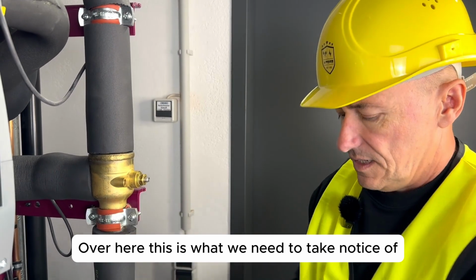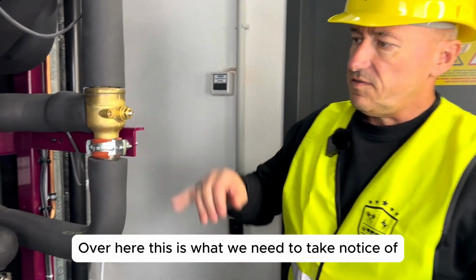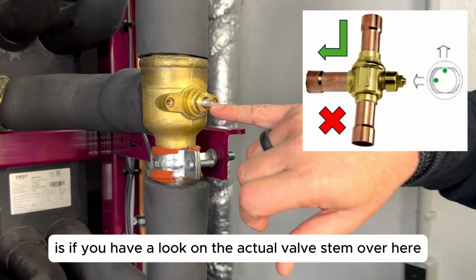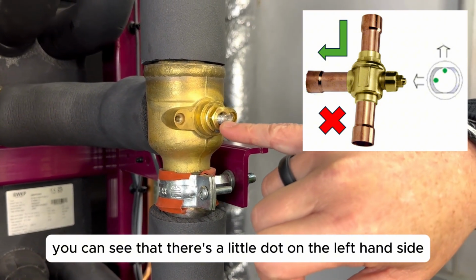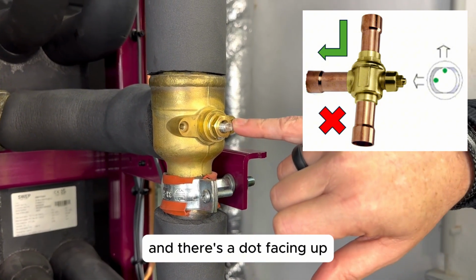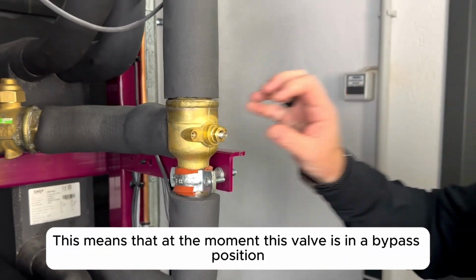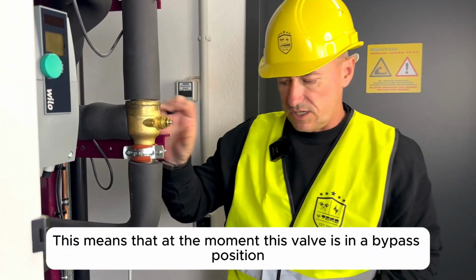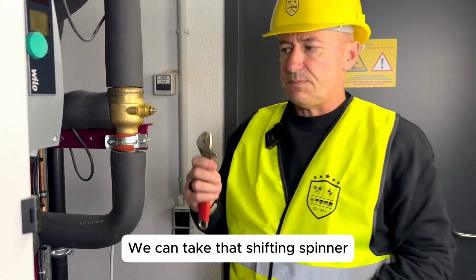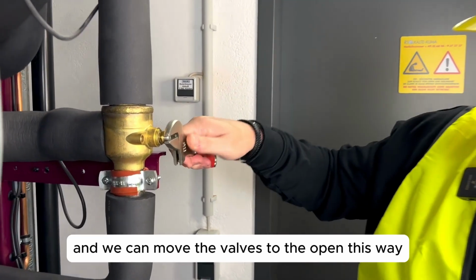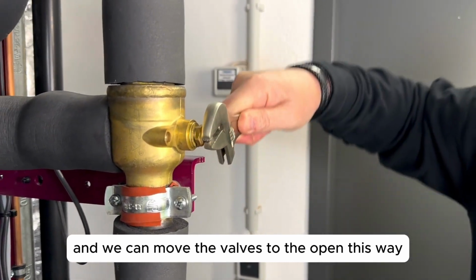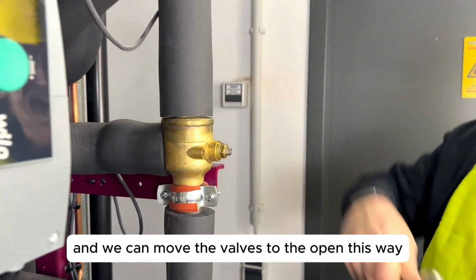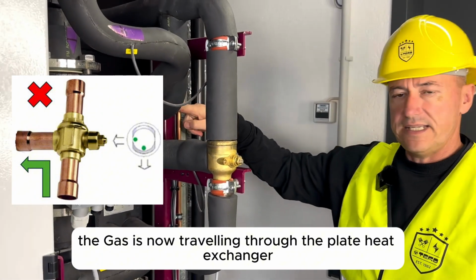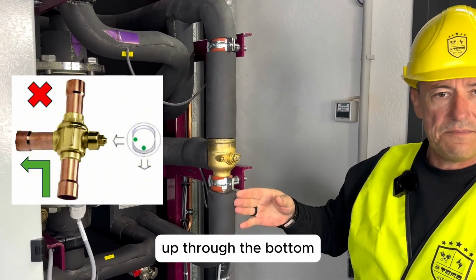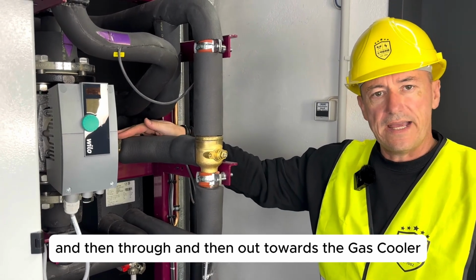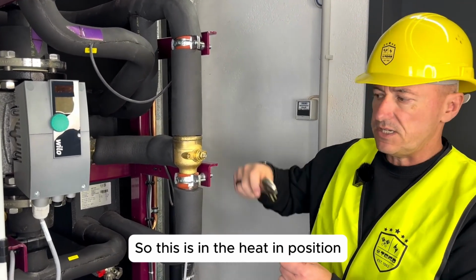Over here, this is what we need to take notice of. If you have a look at the valve stem over here, you can see that there's a little dot on the left hand side and a dot facing up. This means that at the moment this valve is in a bypass position. We can take our shifting spanner and move the valve to the open. This way the gas is now traveling through the plate heat exchanger, up through the bottom and then through and out towards the gas cooler. So this is in the heating position.